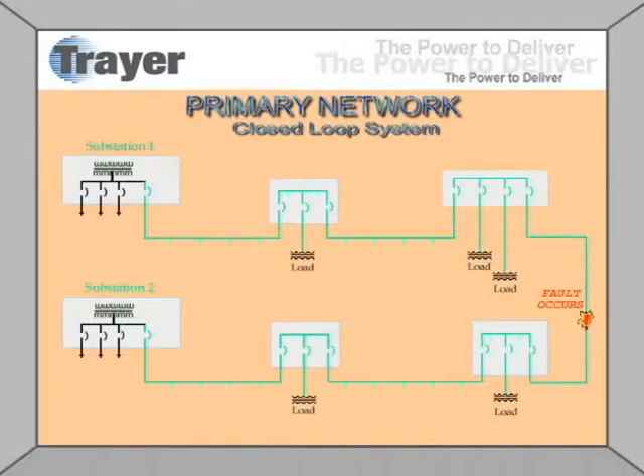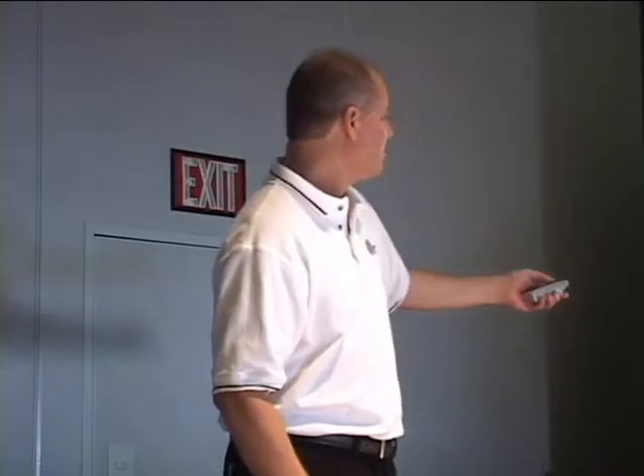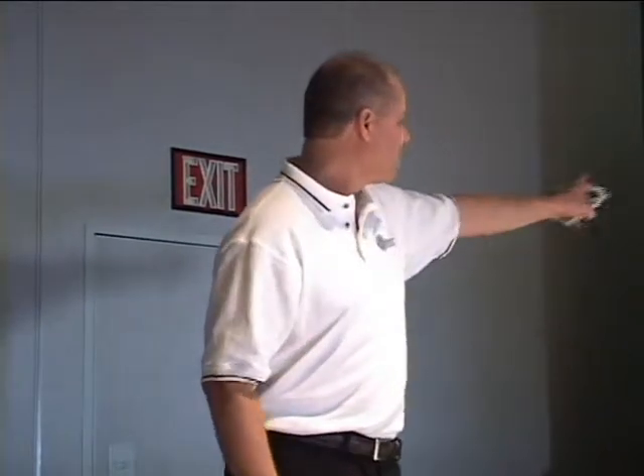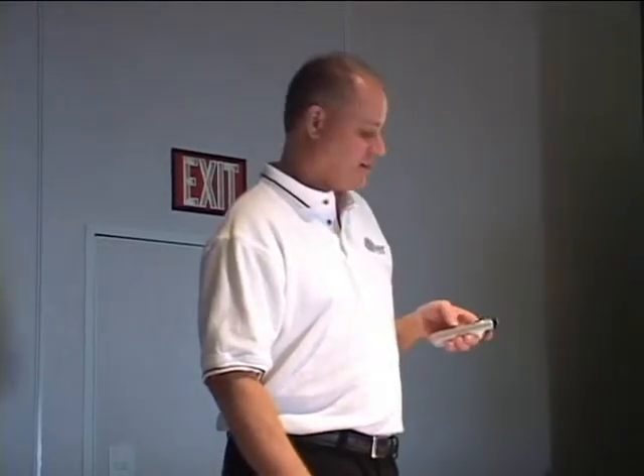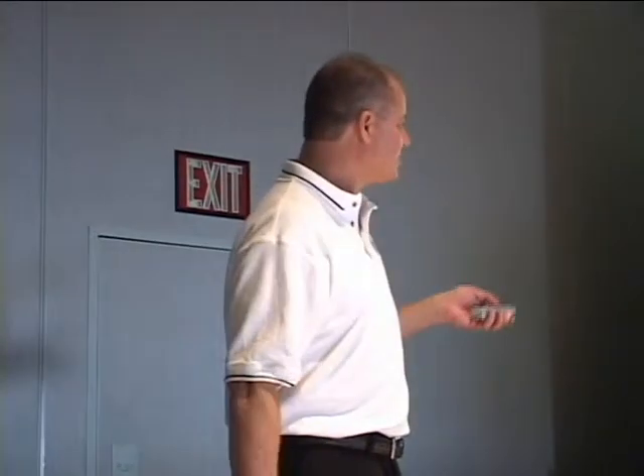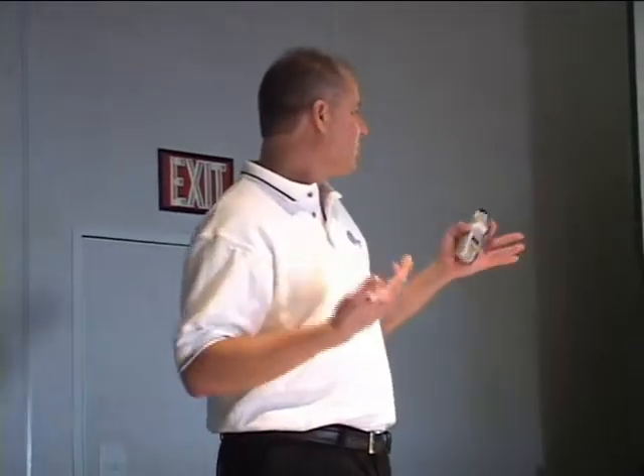Let's take a look at something else. What happens when we have a fault? Well, we're going to get fault current contribution from both of these substations, aren't we? And the available fault current is going to be whatever your system voltage is divided by the fault impedance. That's going to give you your maximum available, it's Ohm's law. That's what your maximum fault current is going to be, and it's not going to be infinite. If this was a zero impedance, we'd have max fault current coming from both subs. It just doesn't happen that way. And let's just throw out a number. Let's say that our system voltage divided by our fault impedance is 10,000 amps available fault current.